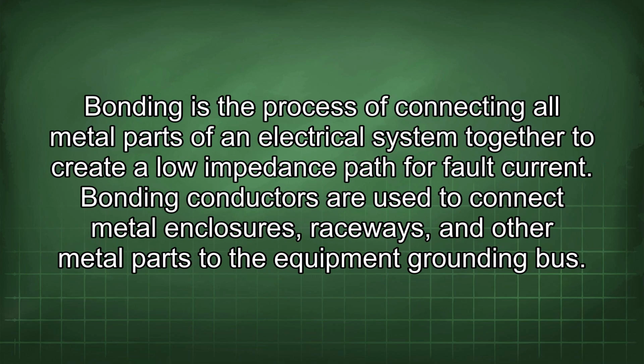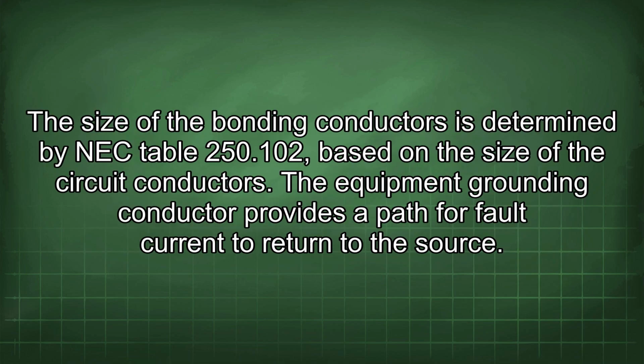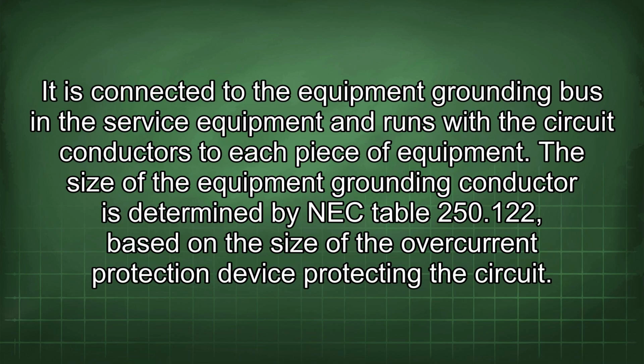Bonding is the process of connecting all metal parts of an electrical system together to create a low impedance path for fault current. Bonding conductors are used to connect metal enclosures, raceways, and other metal parts to the equipment grounding bus. The size of the bonding conductors is determined by NEC Table 250.102 based on the size of the circuit conductors. The equipment grounding conductor provides a path for fault current to return to the source. It is connected to the equipment grounding bus in the service equipment and runs with the circuit conductors to each piece of equipment.